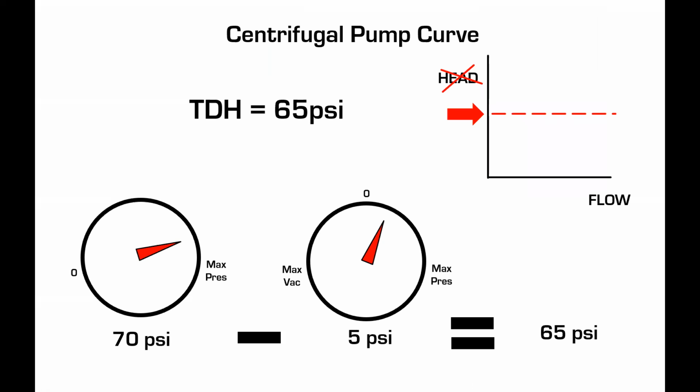Does that make sense? It's always a bit in the weeds. No, I think it makes sense. Take a PSI reading on your gauge, but just make sure you understand that fluid and make sure you know the specific gravity of that fluid prior to comparing your gauge reading to the pump curve. Exactly. Most of the time, we probably get away with it because most things that are pumped in this world are water-like, but it's the times when you don't get away with it, it gets you.